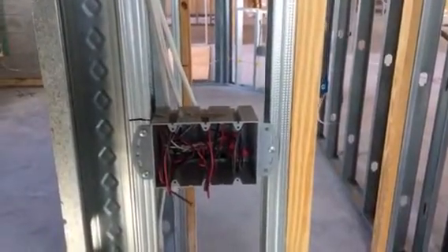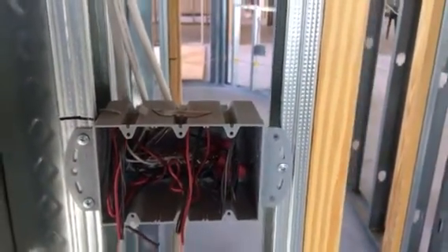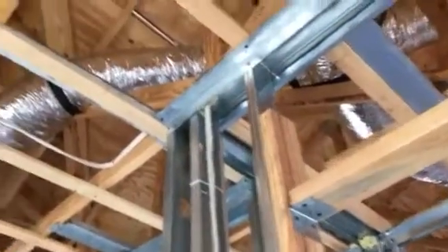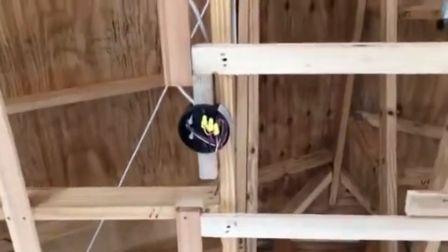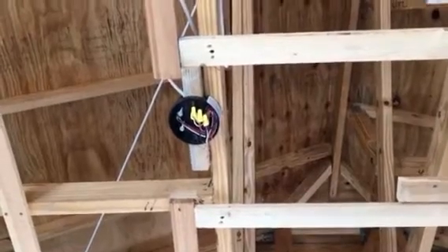What I want to talk about today is wiring your typical bedroom, and we'll walk through the house. This is a three-gang box — nice and neat, everything's running to the side, strapped up nice and neat. This three-gang box goes to a fan; this is a fan-rated box. We always run 14-3 wiring to it.